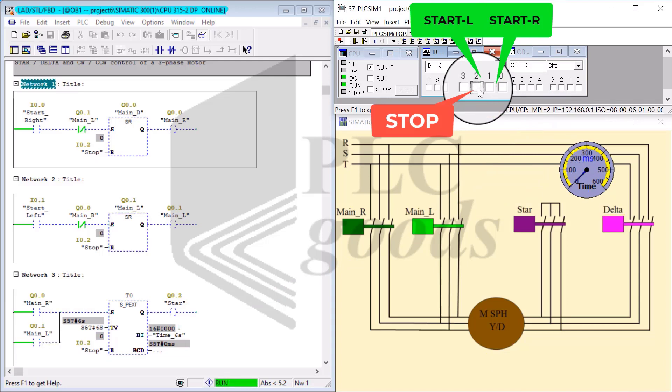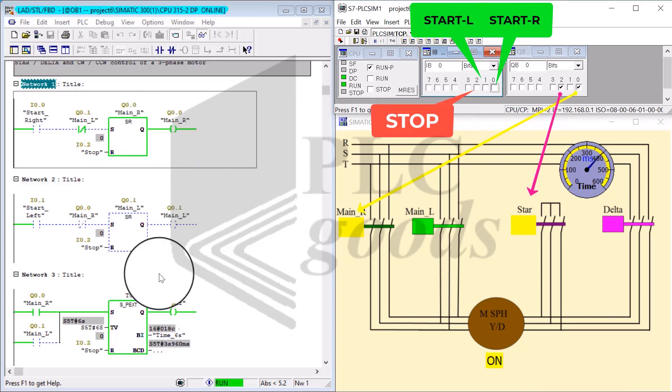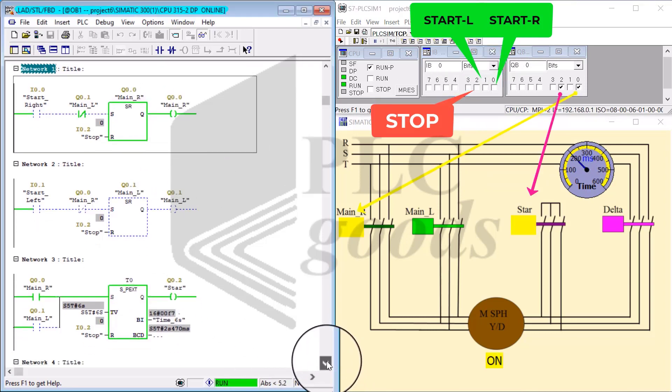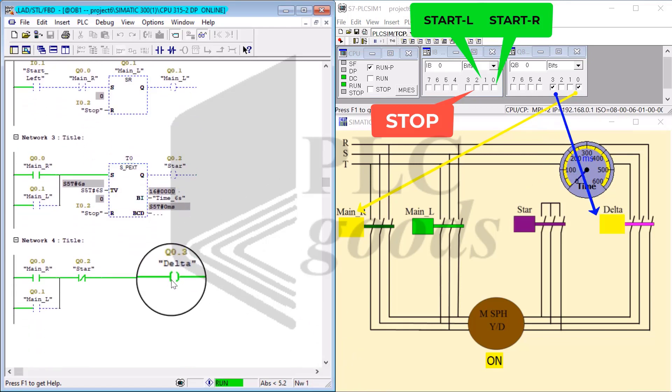I go ahead and stop the circuit again and tap on the start R push button this time. Notice the same process happens: first main R and star, and after six seconds delta contactor kicks in.